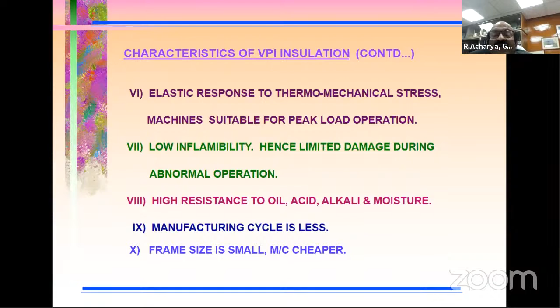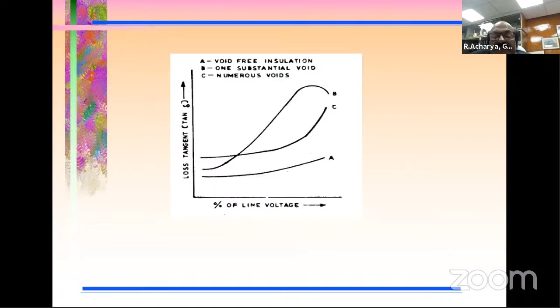You can see over here different kinds of void-free insulation systems. Normally, with the resin-rich insulation system, individual bars have more voids, whereas a resin-poor, total impregnation insulation system is almost void-free. One important thing for the operators, basically power plant owners: what is the advantage to them? It is a long service life and less maintenance, because unlike the resin-rich system wherein individual coils have to be inspected and the tightness has to be checked every year, you have to plan for maintenance and all that.